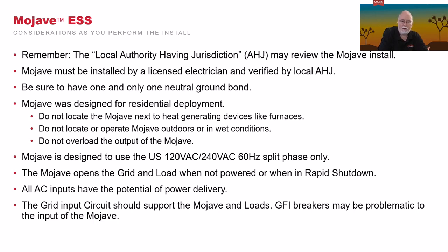Mojave was designed for residential deployment. So install it in an area that is non-occupied space. This would be like in a garage or a closet, but make sure that it's away from heat generating sources. Make sure that it's above where you'd expect floodwaters to come in, if you need to raise the floor, but make sure the floor is sustainable to hold the battery, and also make sure that it's level. Do not overload the Mojave. It just goes without saying. Inverters work great. We have a good surge capacity on this one, but don't operate it in a surge element all the time. Just not good for it.